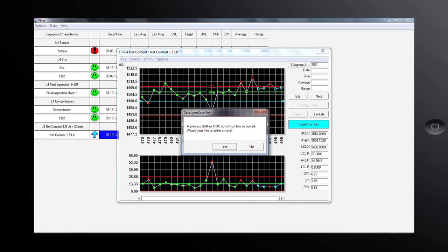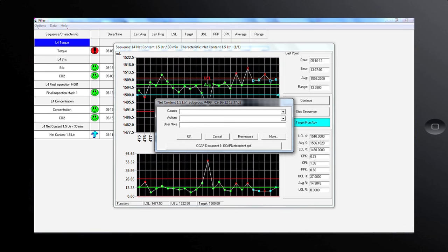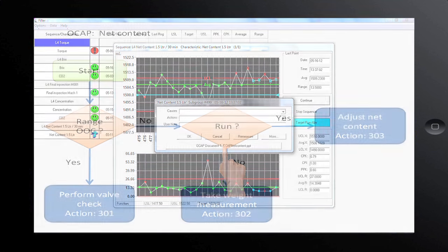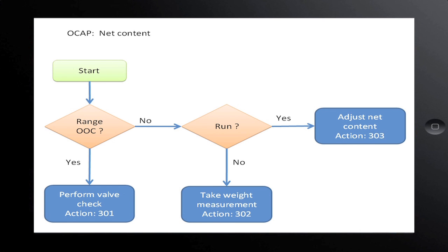When the process is out of control, there can be different causes. The process of an individual valve might have changed, or the total process average might have changed. The type of out of control and the pattern on the control chart can provide the operator with the information to find the cause quickly. With less experienced operators, we can assist them by showing an out-of-control action plan. From the note screen, the operator can start the action plan — a flow chart guiding the operator through how to handle an out-of-control process. The exit points of the flow chart show a cause and action that can be selected in the note screen.